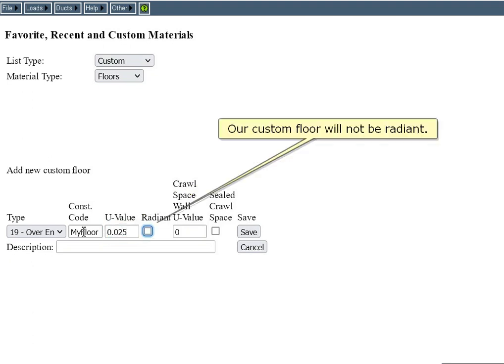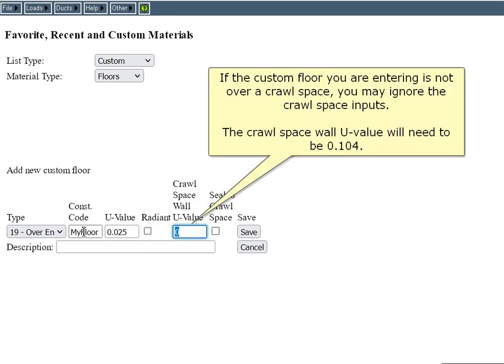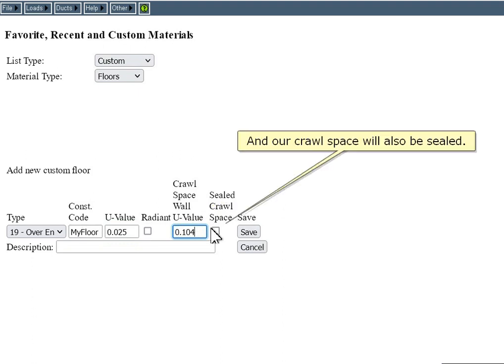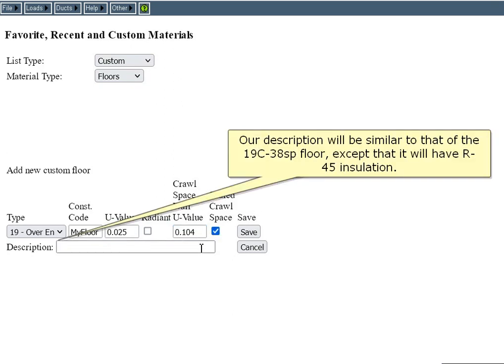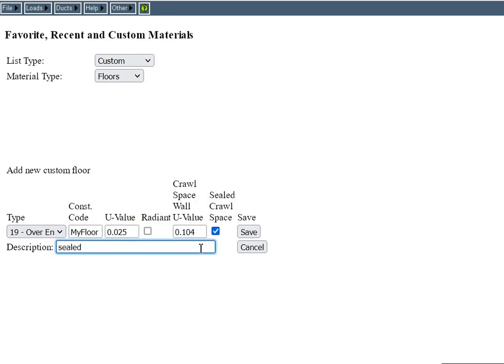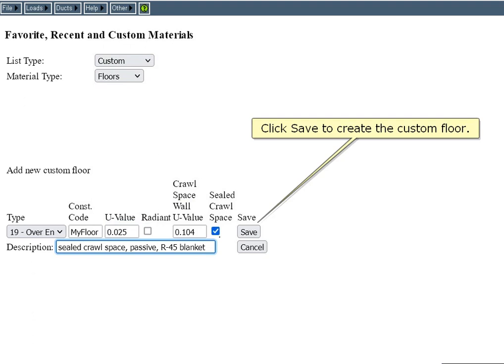Our custom floor will not be radiant. If the custom floor you're entering is not over a crawlspace, you may ignore the crawlspace inputs. The crawlspace wall U-value will need to be 0.104, and our crawlspace will also be sealed. Our description will be similar to that of the 19C-38SP floor except that it will have R45 insulation. Click Save to create the custom floor.